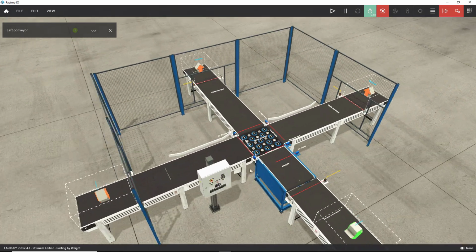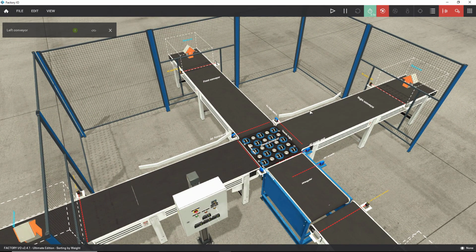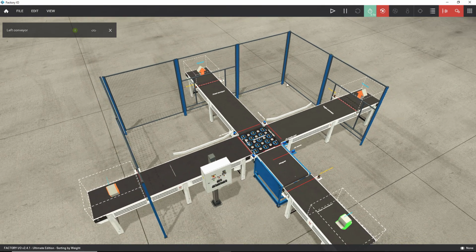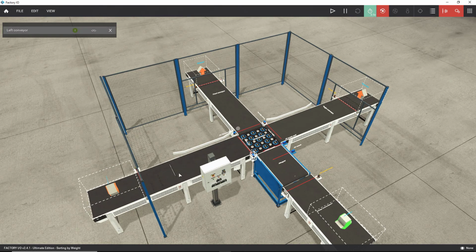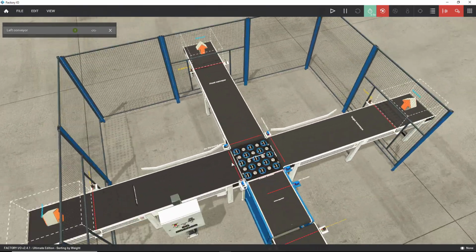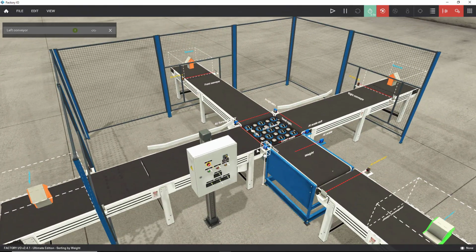And the nice thing is with these functions, you could have 12 different paths all controlled. If we changed this up slightly and you had to go straight and then you had to peel left, peel right, so that way you could do 5 different weights. You could go left 1, left 2, straight, right 1, right 2. It would again be that same function. You just have to call that new function and say, the input for it is this, the other output for it is this, and the conveyor name is this. So you'd have one output, 2 inputs that you'd be passing into that, and maybe another output saying there's a part on it or not a part on it, depending on if the system's working. So it simplifies your life a lot when you are dealing with this.